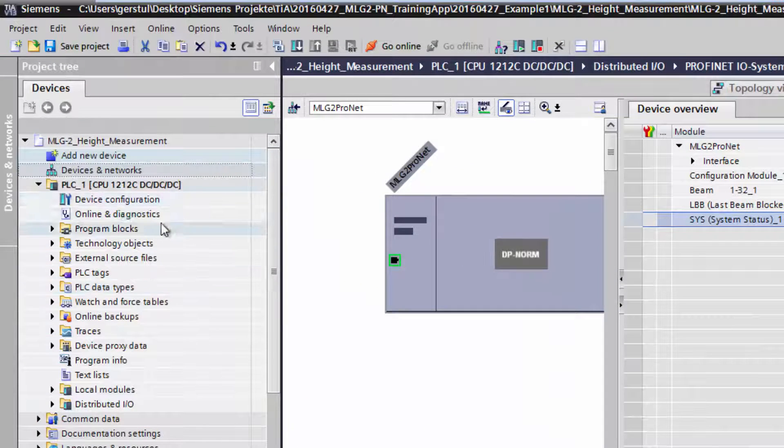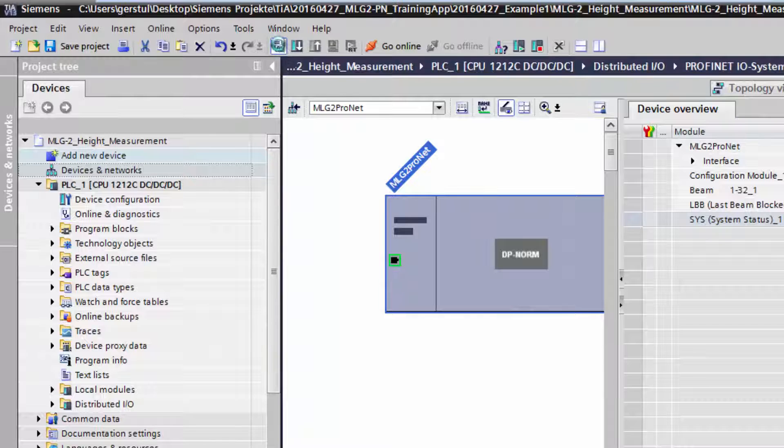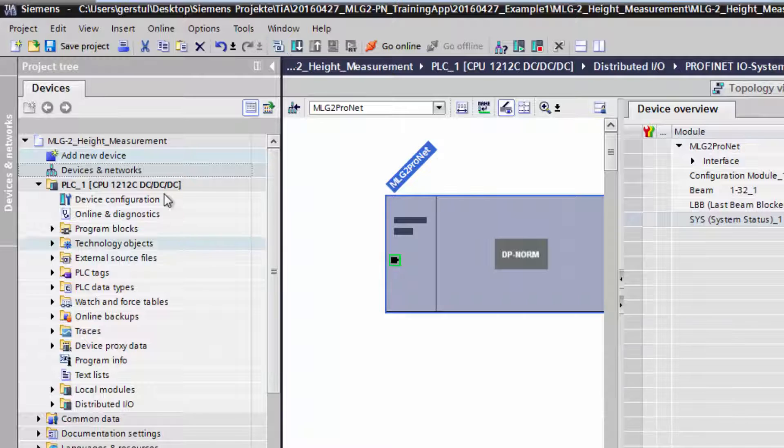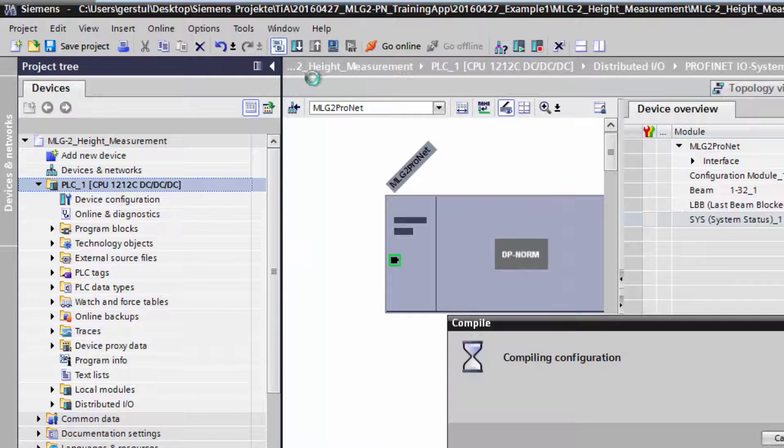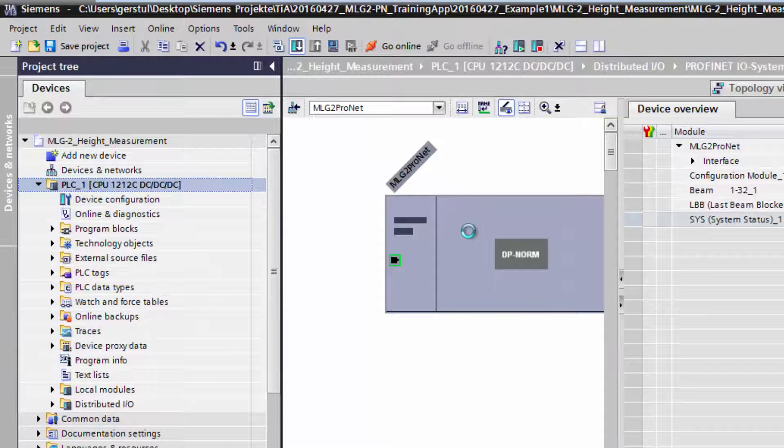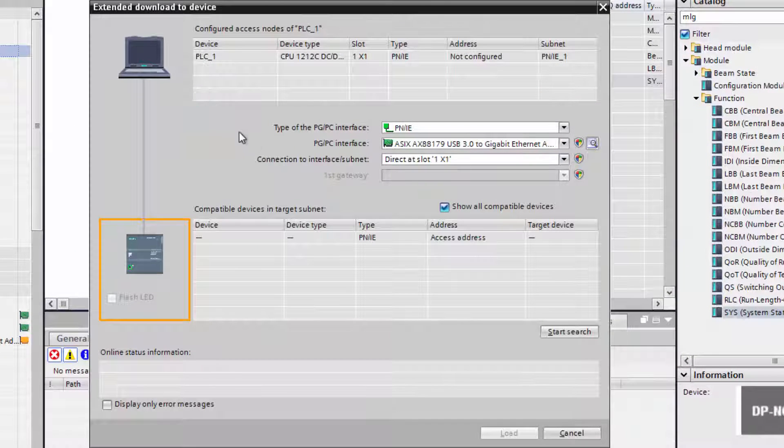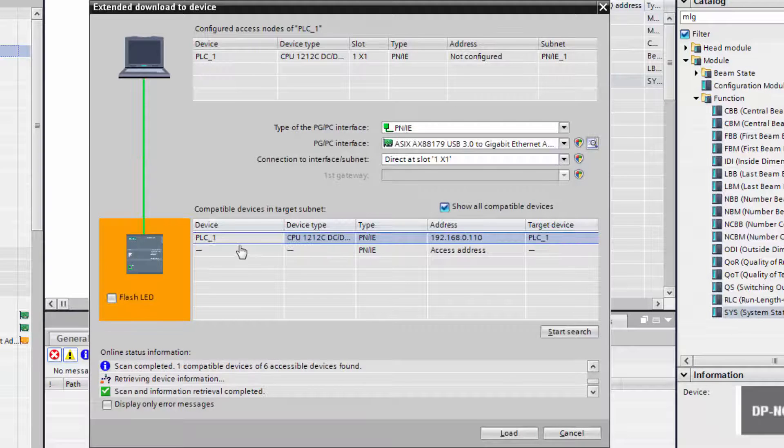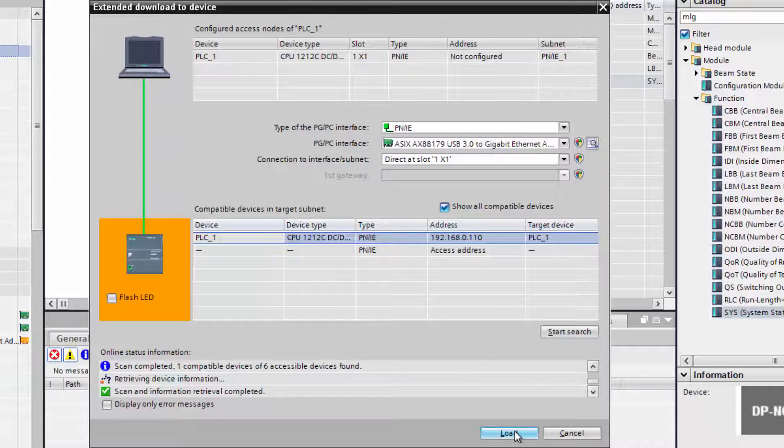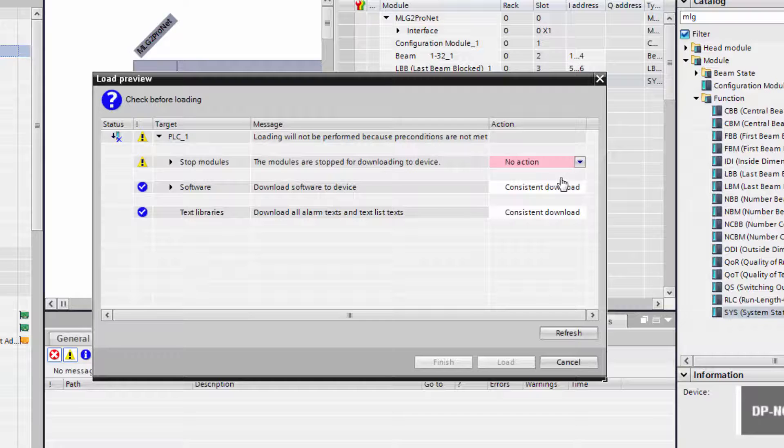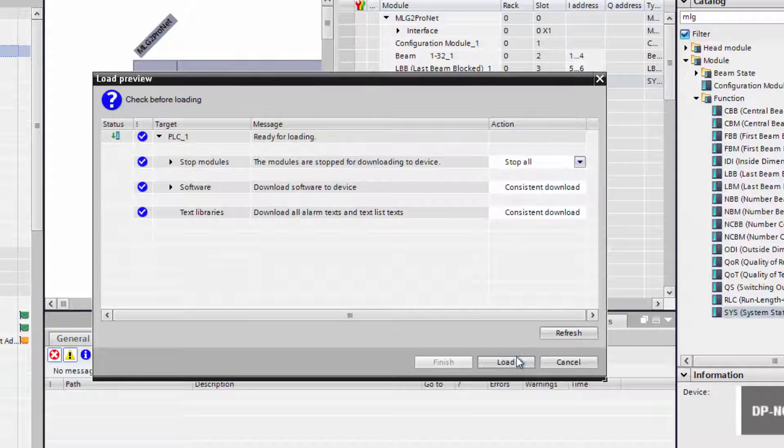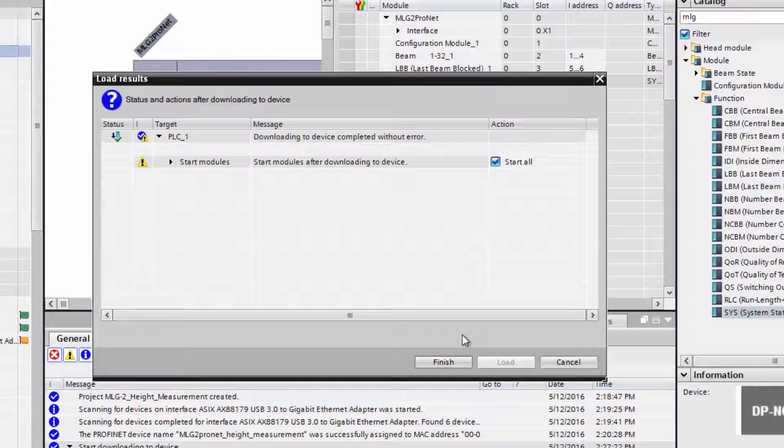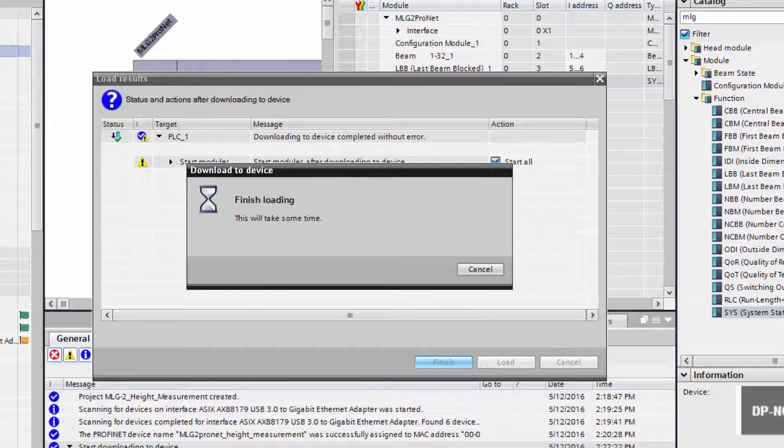Select the device and click on Compile in order to compile the configuration. Click on the PLC, compile again and download to the device. Click on Start Search in order to find the connected devices. Select the PLC and then click on Load. When the load preview is finished, click on Load again. Then restart the PLC by ticking the box Start All and then clicking Finish. The configuration is done.